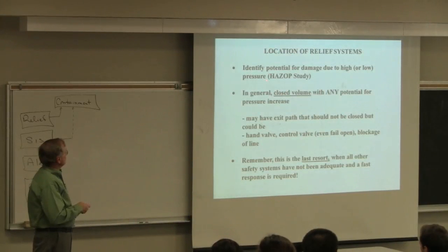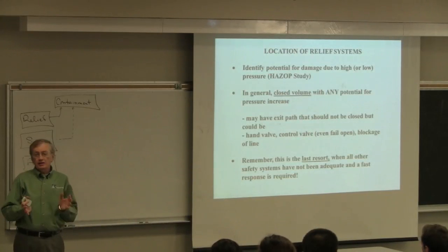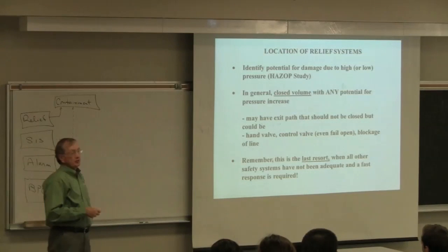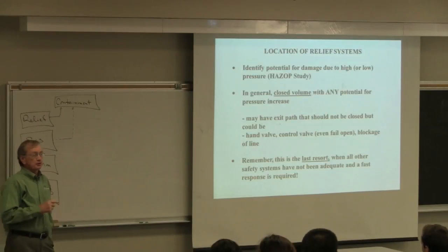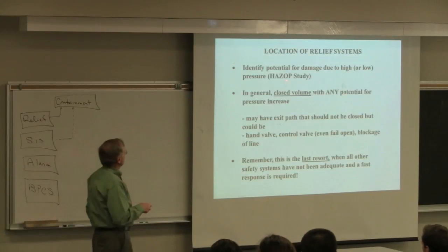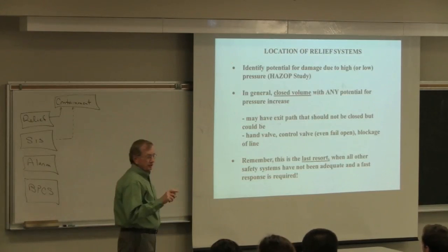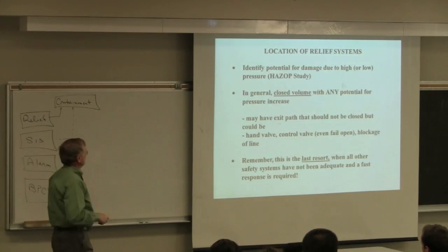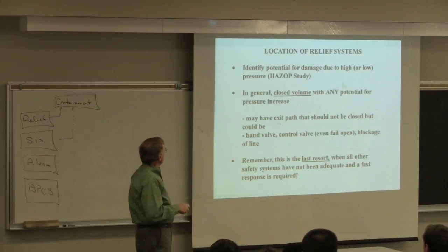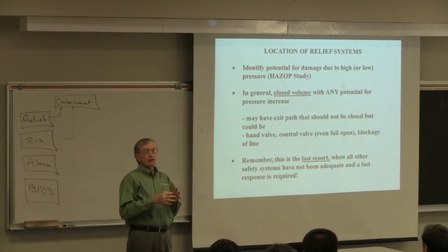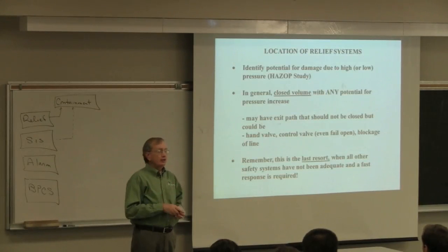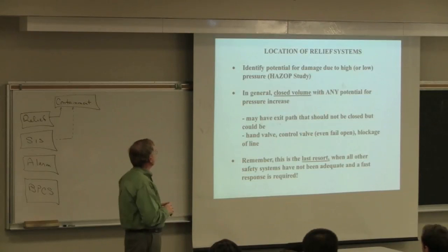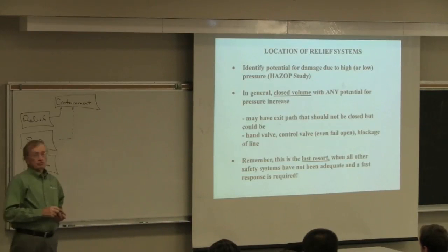To know where to install relief devices, we'll get some guidelines, and then as we go through the process with a hazards and operability study in the next class, we'll identify the specific locations. Generally, any closed vessel—any vessel where all inputs and all outputs can be entirely shut off—needs pressure relief.